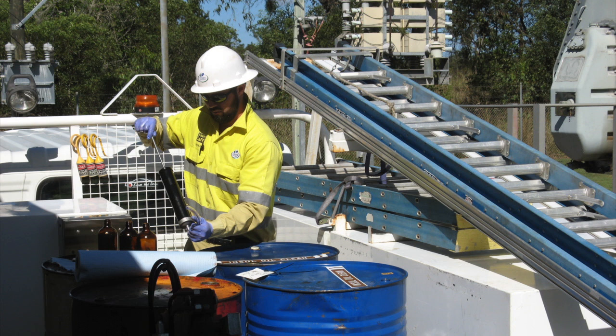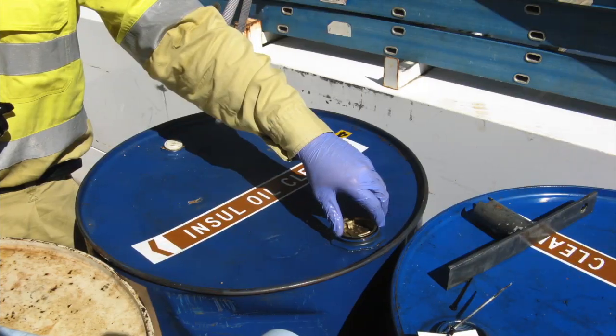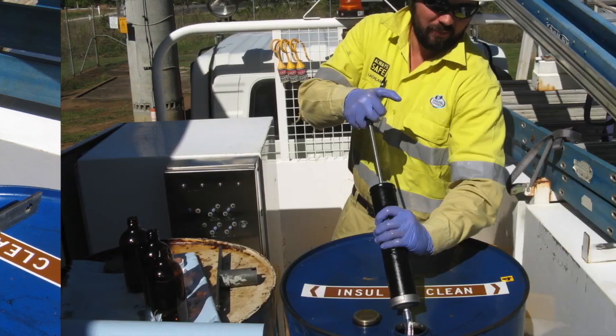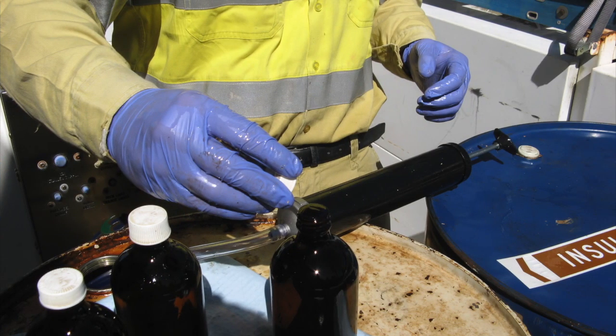When you're out in the field, take your sample on the day that you're going to actually install it into the HV plant. The reason being is that oil will degrade somewhat throughout the time that you have it on site.